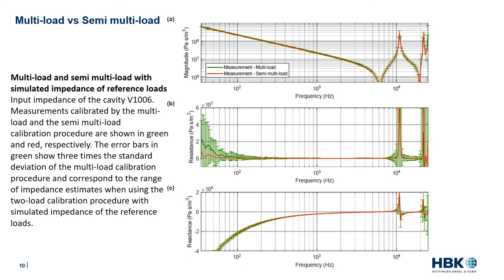The two-load calibration procedure can be further improved by measuring on more than two known reference loads, yielding an over-determined set of equations for finding the unknowns. However, this requires all reference loads to be measured at any measurement session, which may be quite cumbersome in an in vivo study on humans spanning several days or weeks. Therefore, we developed a simpler method called the semi-multi-load, where only two reference loads — as with the two-load method — are measured at each measurement session. The calibration is then performed as post-processing involving measurements on all reference loads only once, and dividing the frequency range in two.